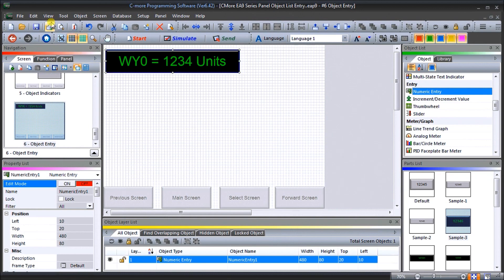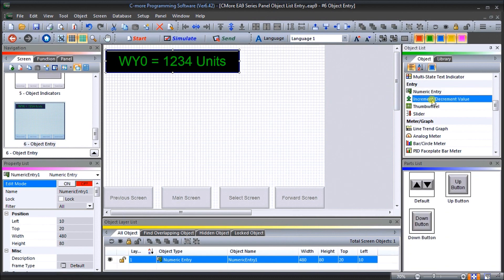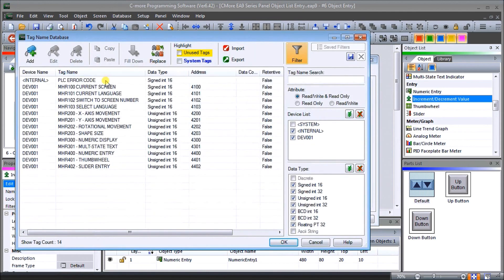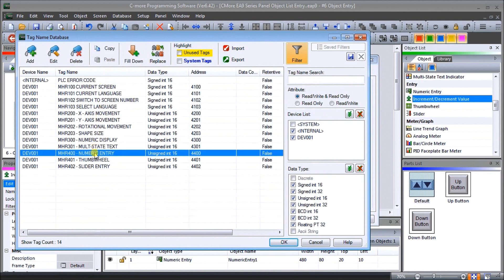Next we'll look at the increment decrement value. We'll take the default up and down arrow key and drag it onto our screen. We'll leave the frame type as default. Under up/down, every time the add button is hit it will add five, and the subtract button will subtract five. Under our read tag name we can set the read and write as two different ones. We won't set the range here — we'll do that in the PLC — and we'll use the same numeric entry tag as before.